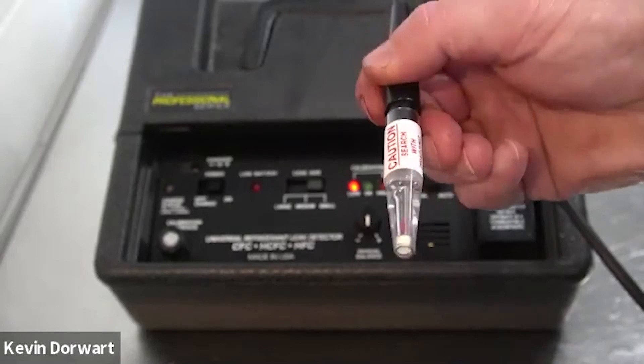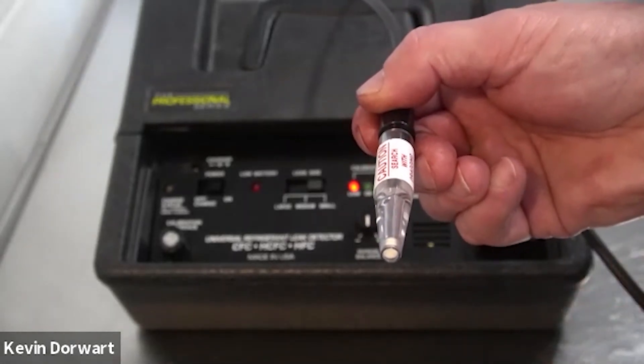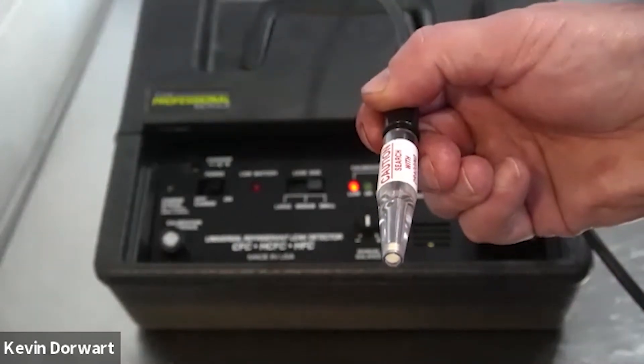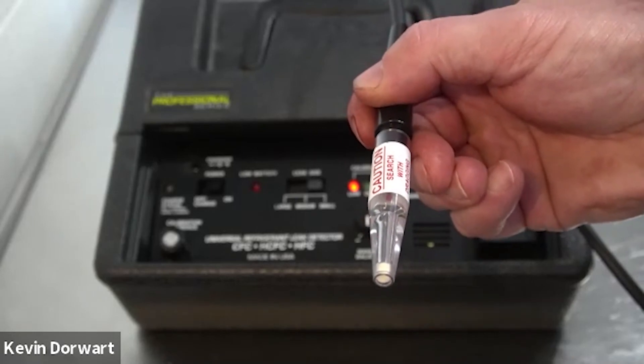The second thing you can try is to remove the filter on the probe tip. Sometimes dirt and moisture will build up in that filter and cause air restriction. If neither of those work, then you will need to return the unit for repair.